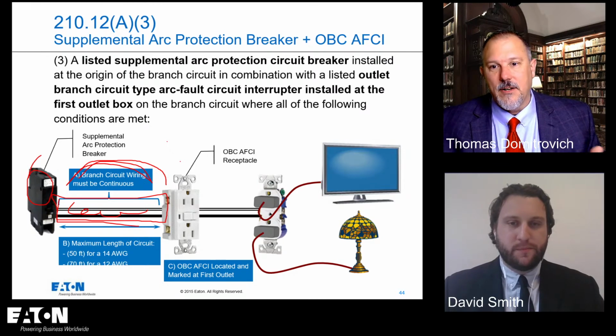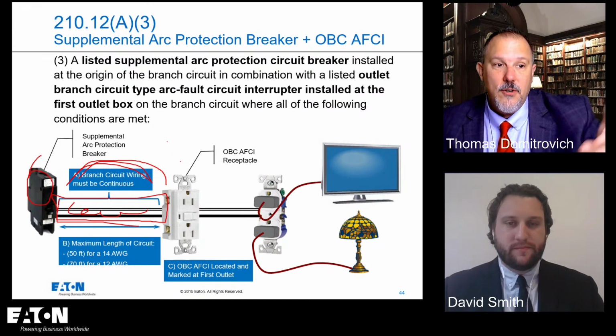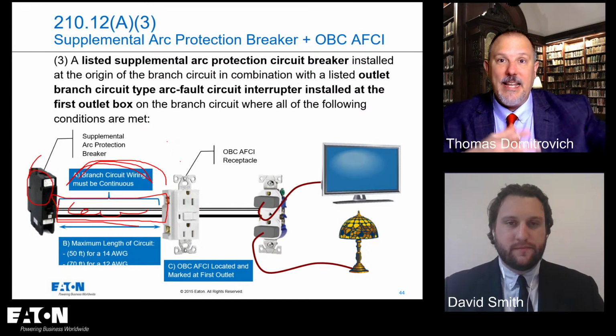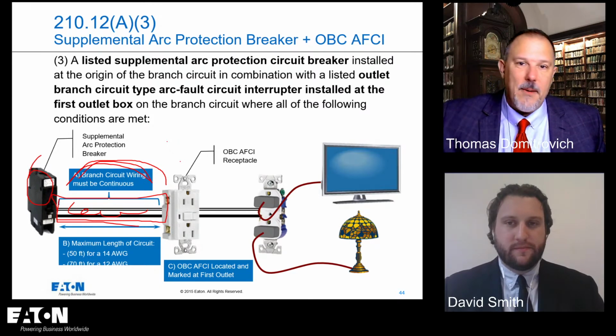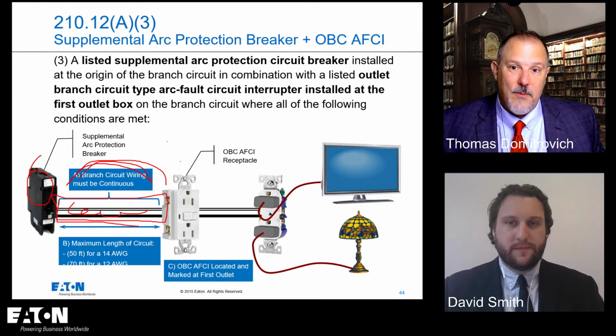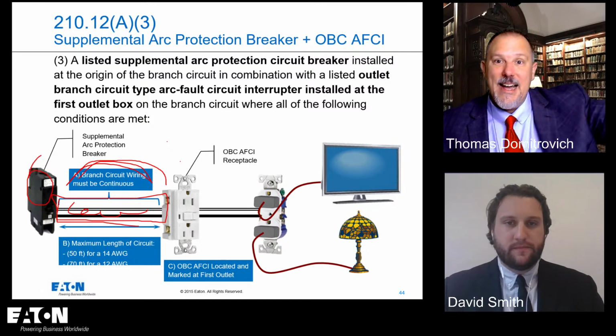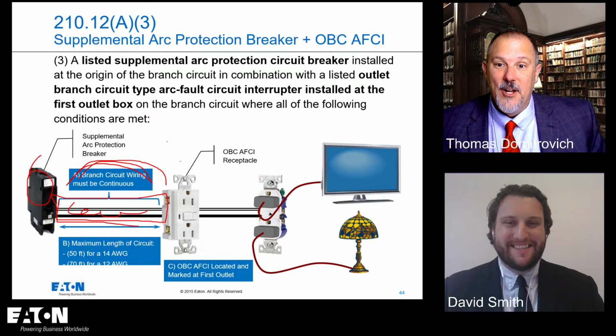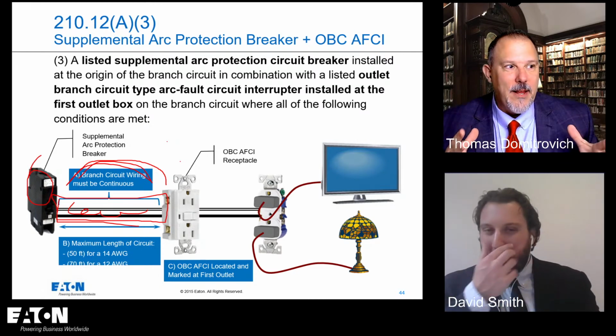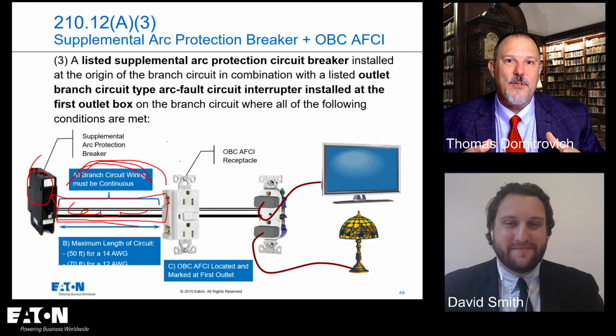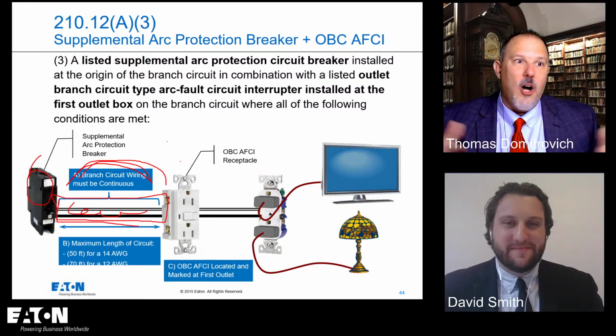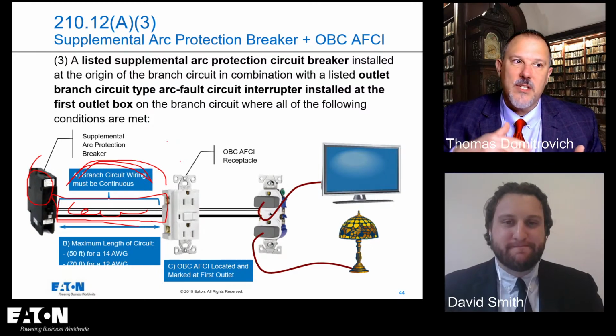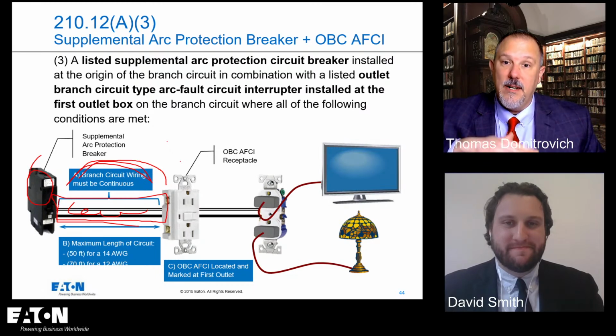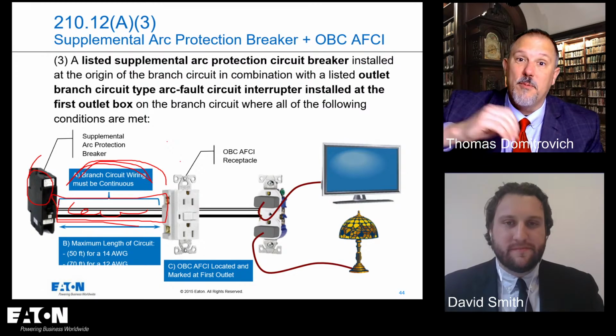And then the breaker guys said, hey, we had Donnie Cook out measuring, and he brought data to the table, and other inspectors brought data to the table. And they said, we're seeing fault currents, my house here in Weirton, West Virginia was below 500 amps. It was 300 and some amps. So we were like, whoa, the fault currents are all over the board. 500 amps is a realistic number for a minimum because you want to make sure you're providing protection.